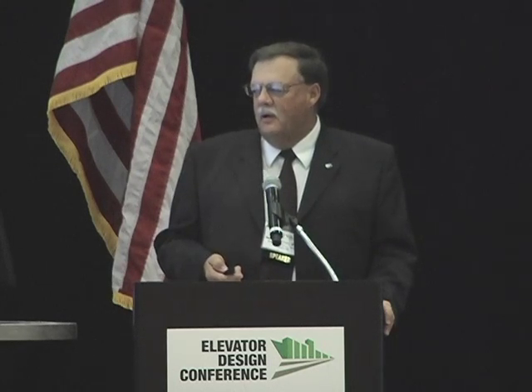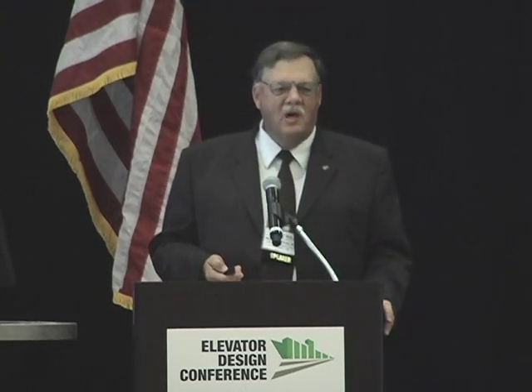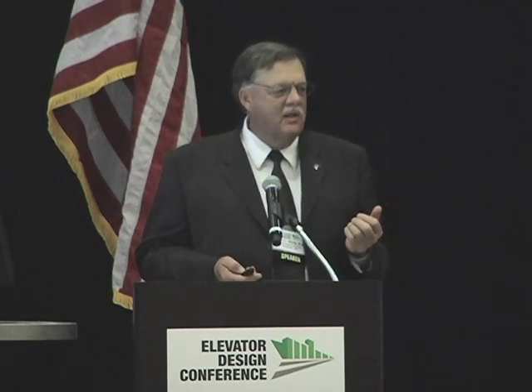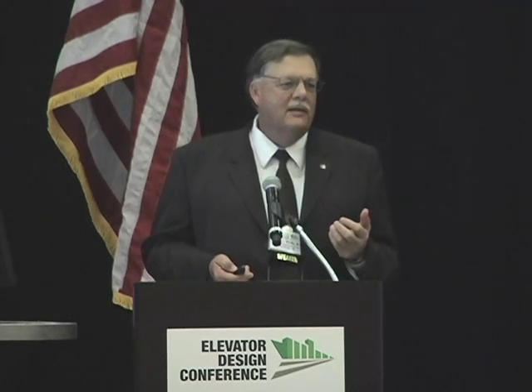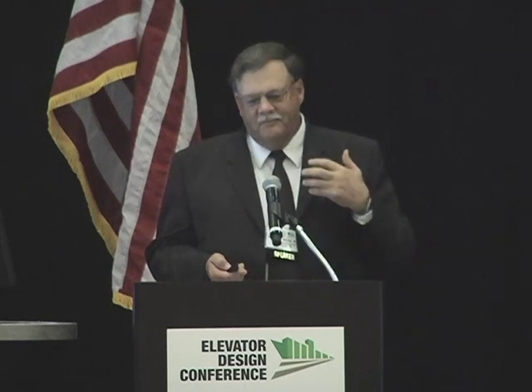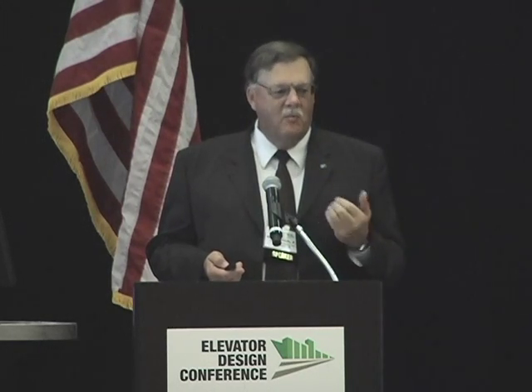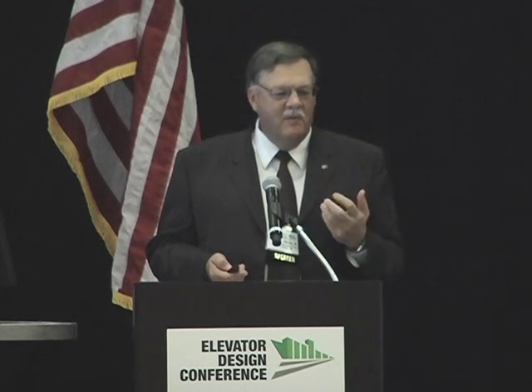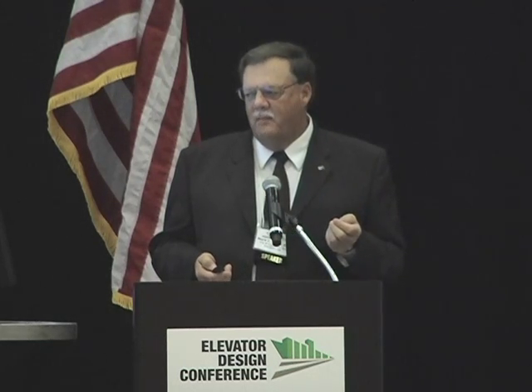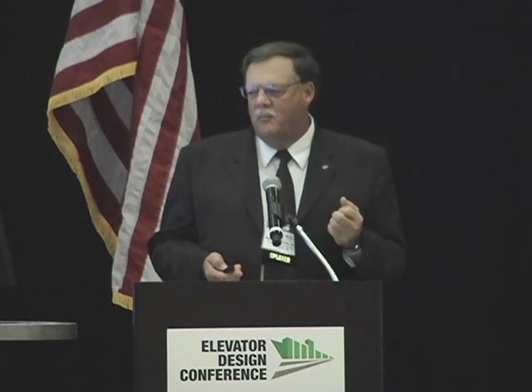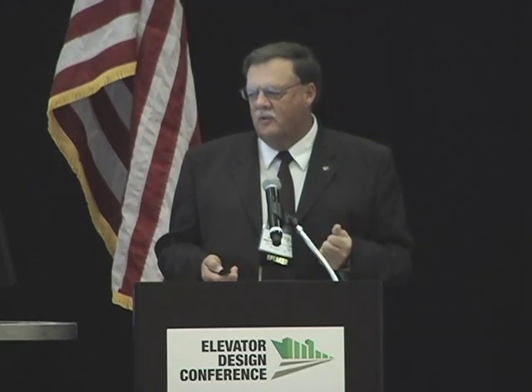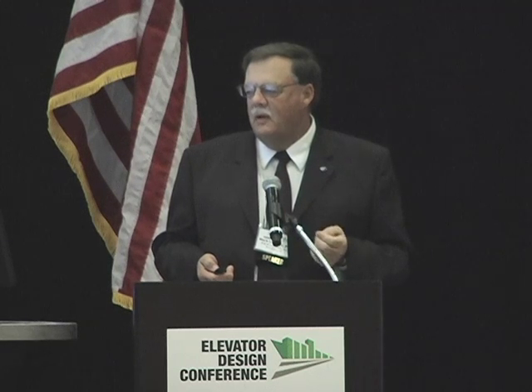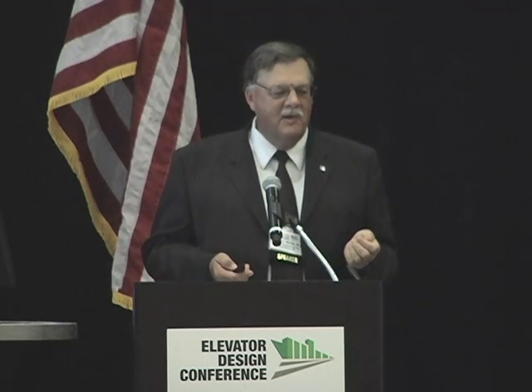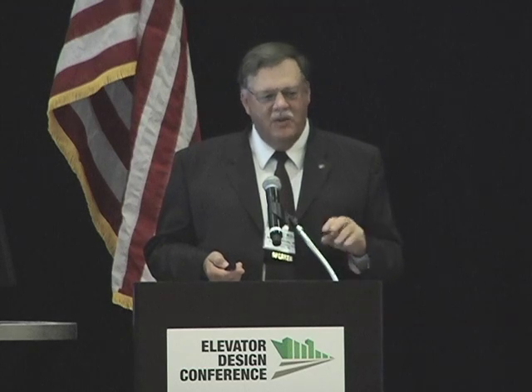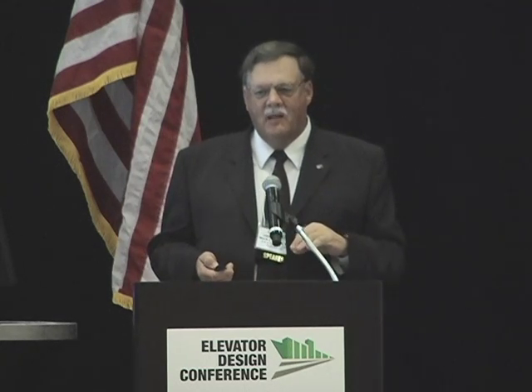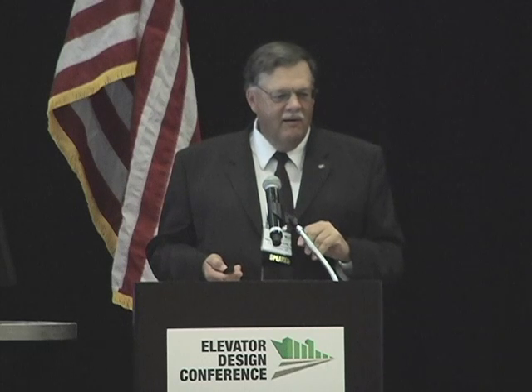The typical 3-phase, 4-wire system is really the predominant power system for all kinds of facilities. In fact, it's so common that as soon as you get much over 25 or 50 horsepower, it's a more common system, and there's so much equipment available for this class of equipment that it becomes the predominant one for any type of industrial system. The drawback of a 4-wire grounded system is when you get a ground, something's going to trip, and it trips immediately. And that means whatever you're doing, you're not doing it anymore.